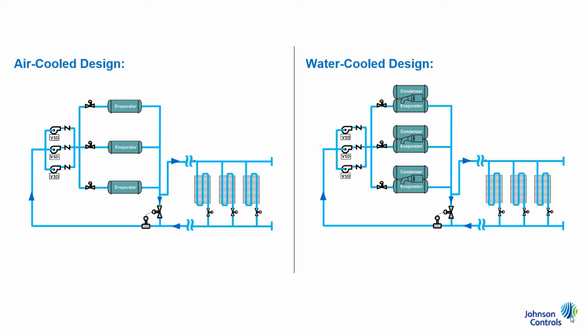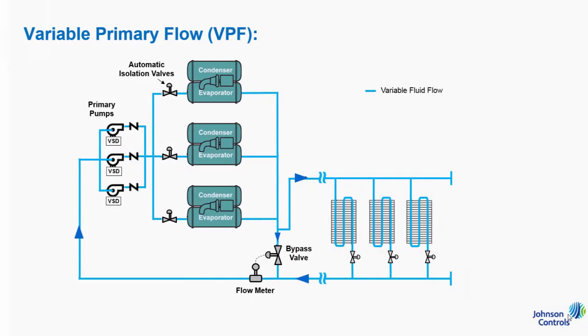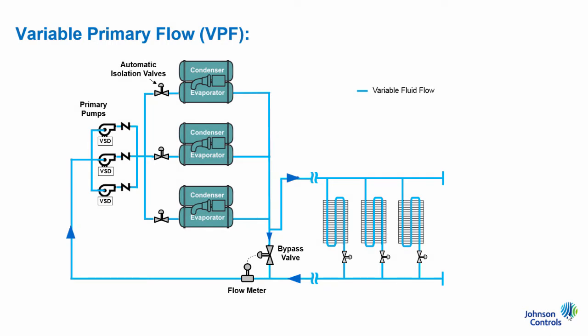Because of its high energy efficiency and low installed costs, variable primary flow has become the industry standard for water-cooled and many air-cooled chilled water pumping system designs. In this video, we will be reviewing an example water-cooled system to learn what a typical variable primary flow pumping system looks like. Additionally, to highlight the key components of variable primary flow, also known as VPF, there will be several comparisons made to the second most popular pumping system, known as constant primary variable secondary flow, or commonly shortened to primary-secondary. So what does a VPF system look like?